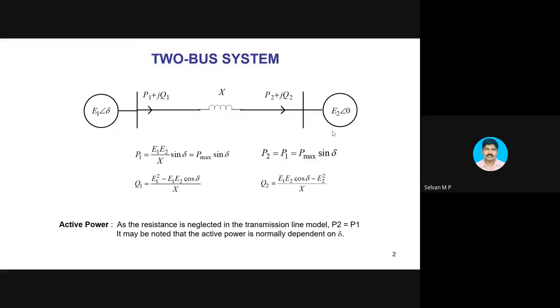Here you have to relate the voltage source converter to a synchronous machine, right? What is a synchronous machine? It is a rotating machine where you will be able to adjust its frequency, phase angle, and magnitude. By adjusting the speed, you can vary the frequency of output. By varying the excitation system, we will be able to adjust the magnitude of the voltage. Of course, phase angle also can be adjusted if you compare with another system. Always the voltage of the load point will have a smaller angle than the internal angle of a synchronous machine. If it is a grid-connected synchronous machine, then the machine will have an internal angle, which is called the load angle, which will be higher than the grid phase. Then only you will have a real power flow, as I said.